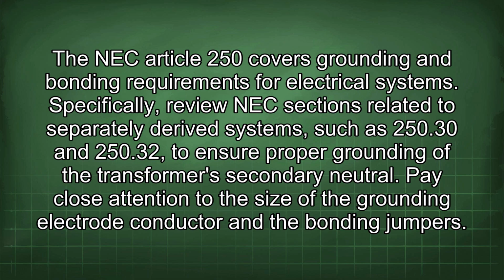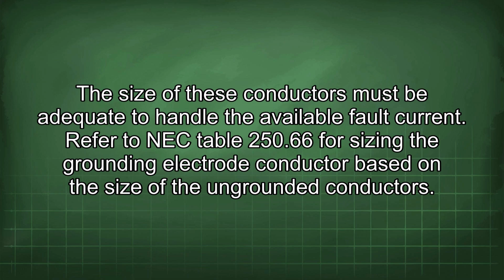Specifically, review NEC sections related to separately derived systems such as 250.30 and 250.32 to ensure proper grounding of the transformer's secondary neutral. Pay close attention to the size of the grounding electrode conductor and the bonding jumpers. The size of these conductors must be adequate to handle the available fault current. Refer to NEC Table 250.66 for sizing the grounding electrode conductor based on the size of the ungrounded conductors.